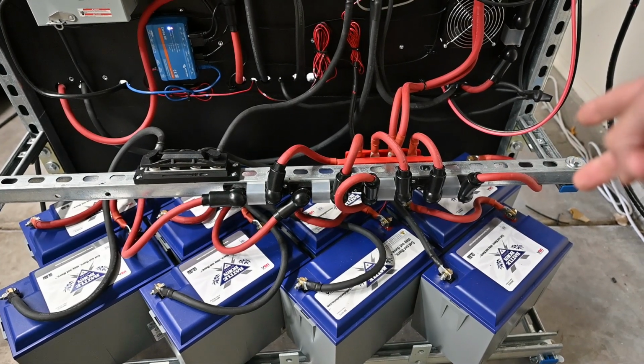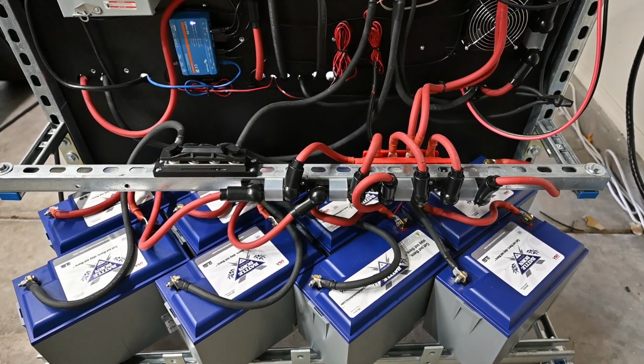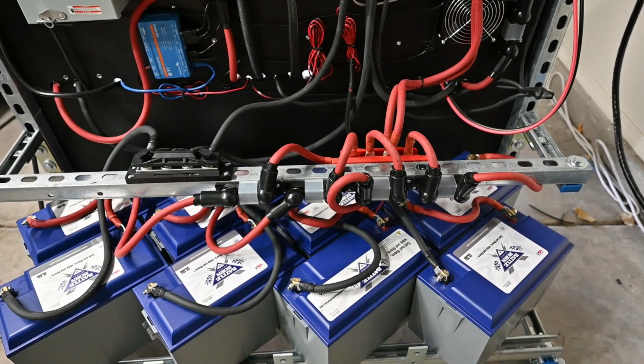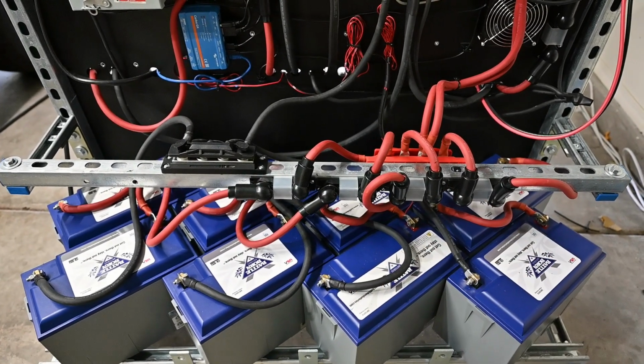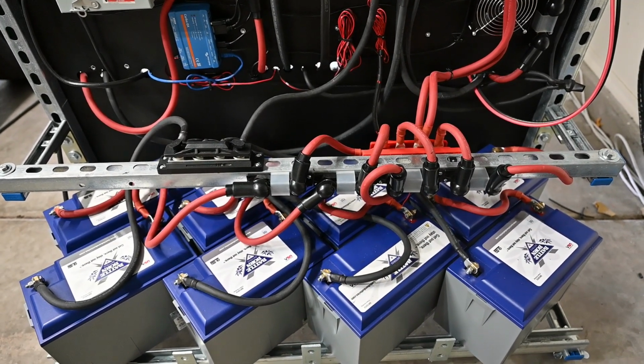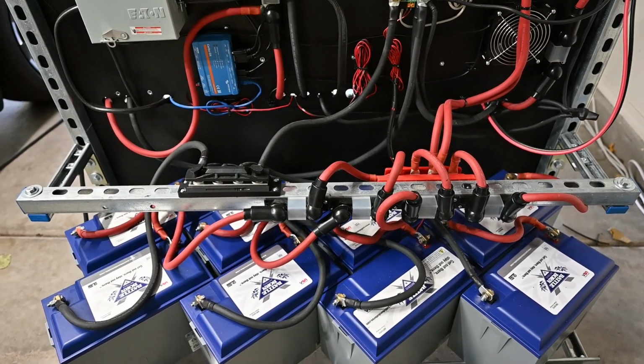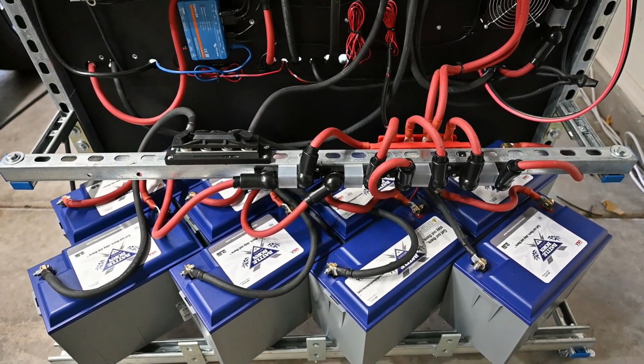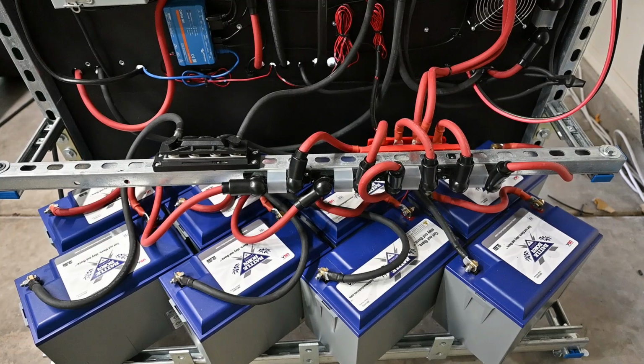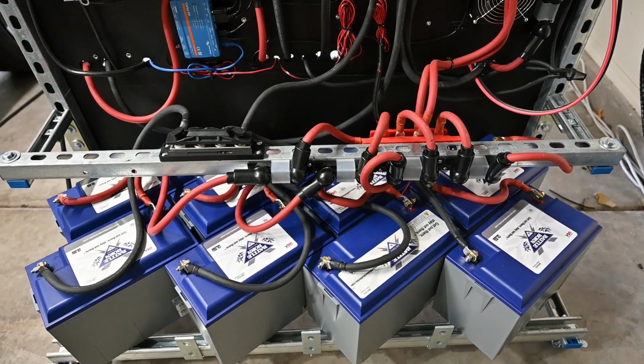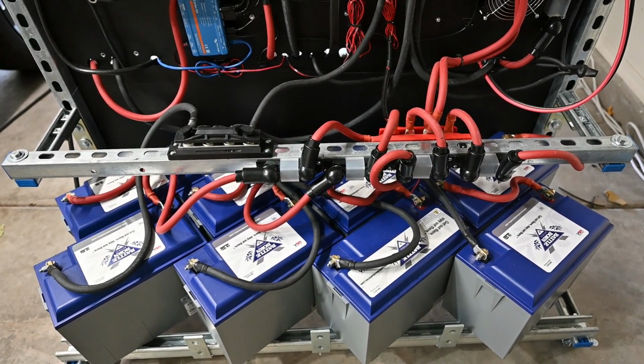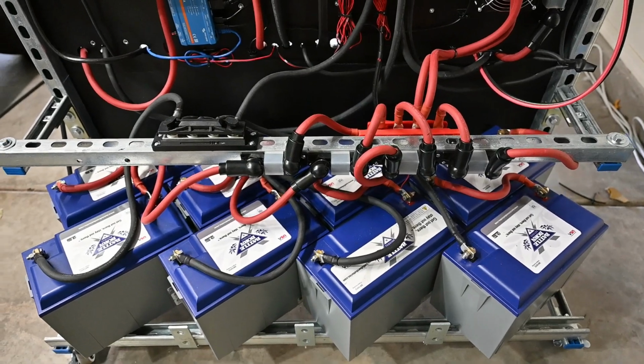There are 4 parallel banks of 24 volts in series. This mess of wires has to be arranged this way because all the leads have to be the same length, so that the resistance is the same, so that all the batteries charge and discharge at the same rate.